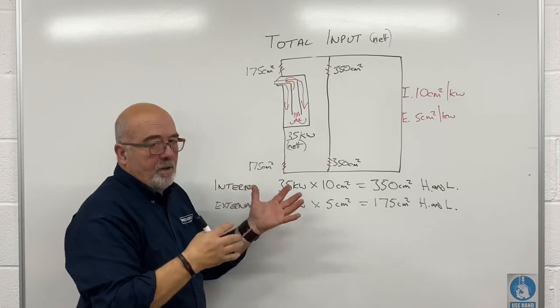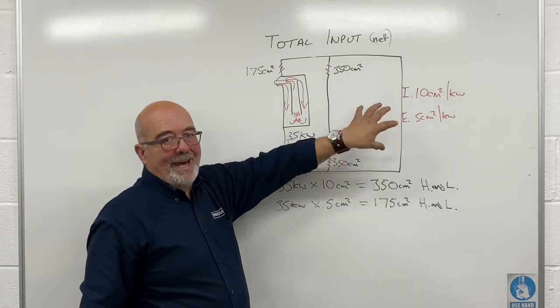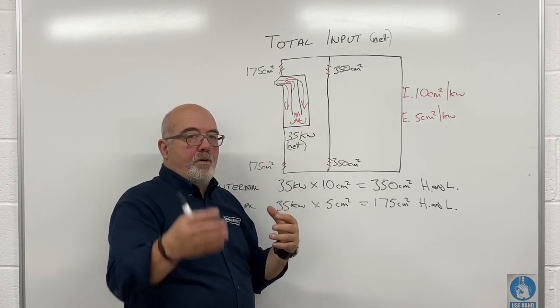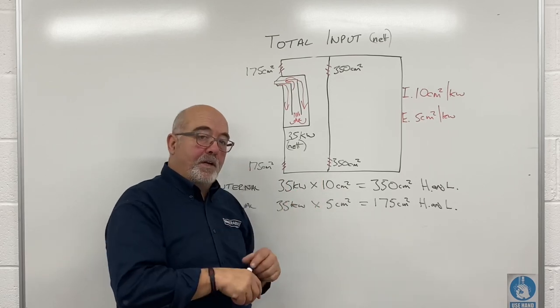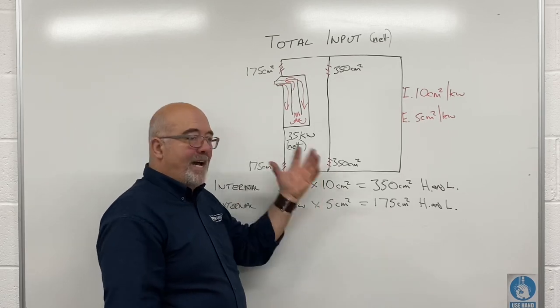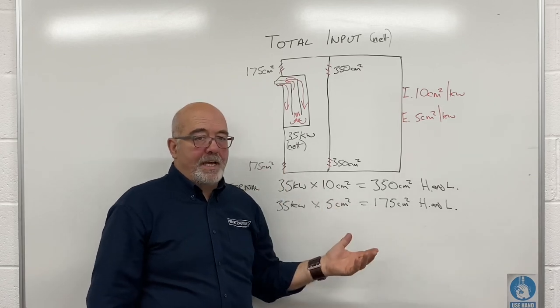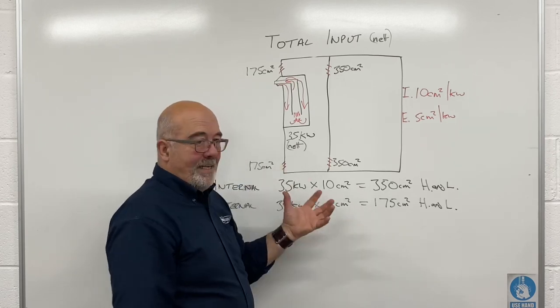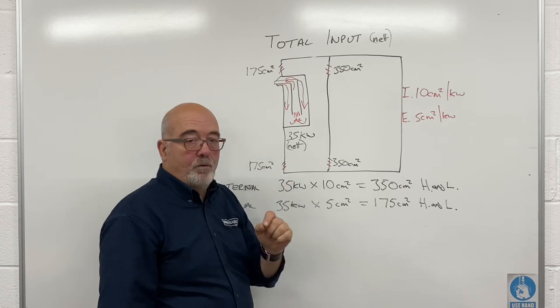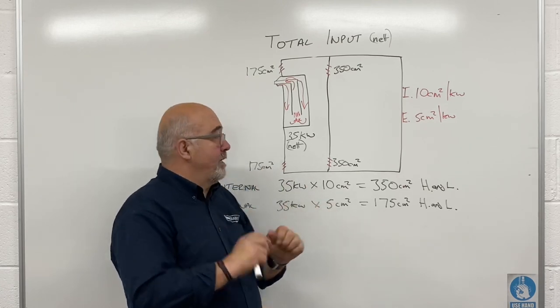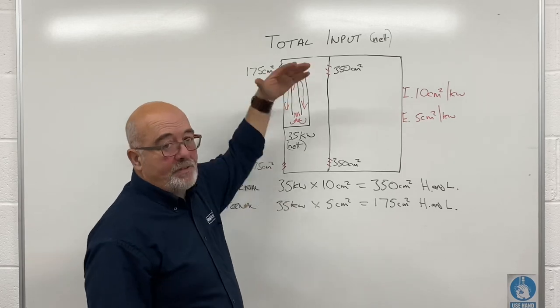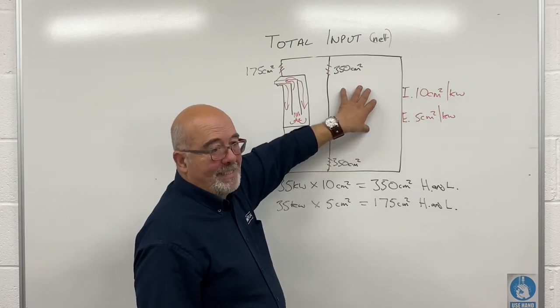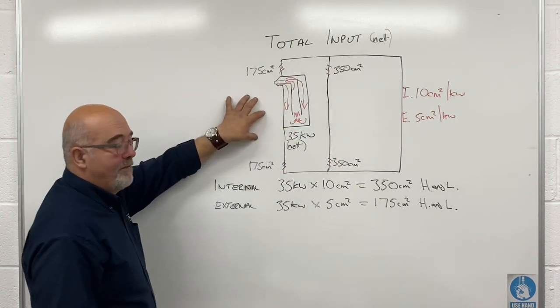Remember why the figures differ: internal air is normally warmer than external air, so you need a bit more air movement to keep the temperature down in the compartment. Again, check the manufacturer's instructions — the majority for the last ten years or so haven't needed compartment ventilation up to a certain input, but do check. It is as straightforward as it looks: total input multiplied by 10 internally, multiplied by 5 externally.